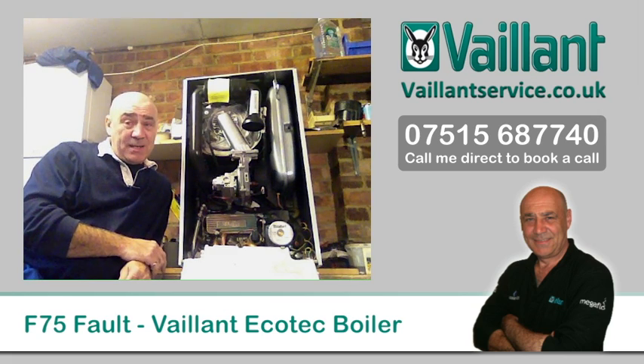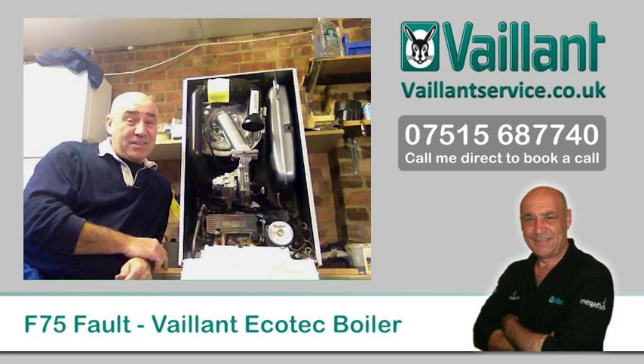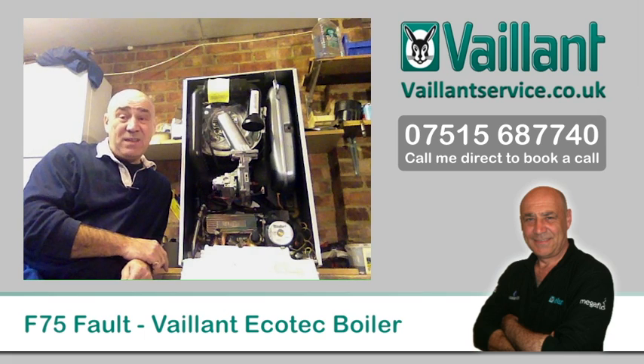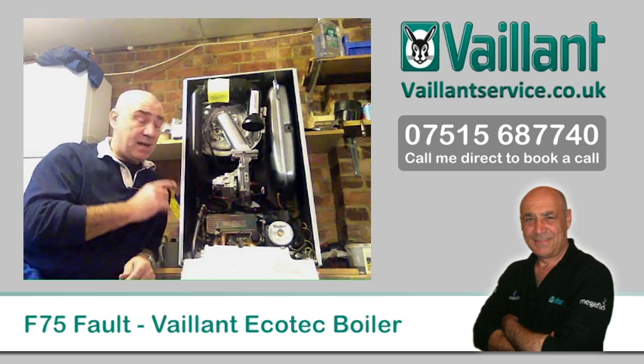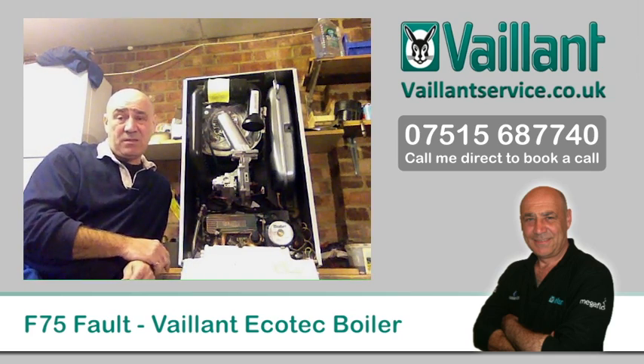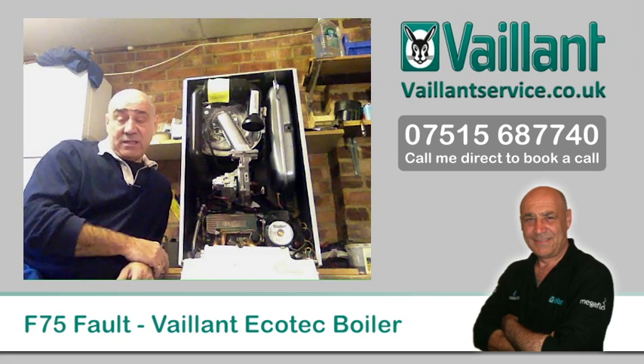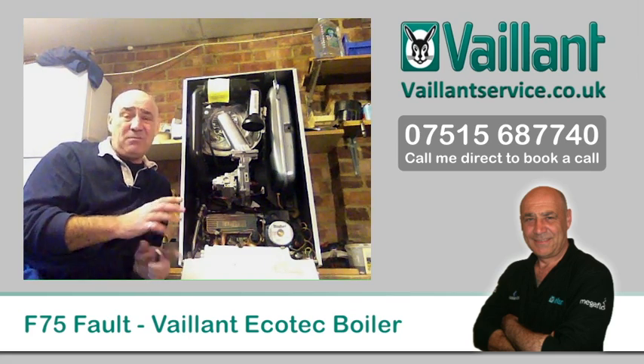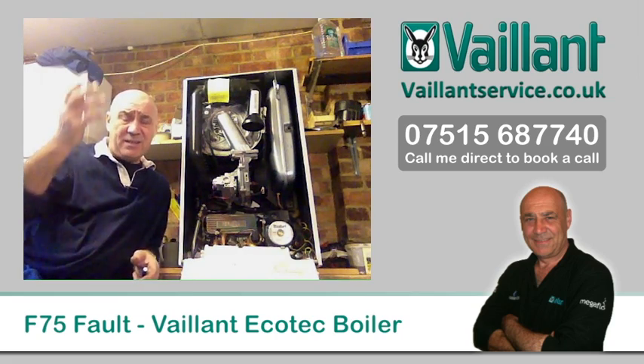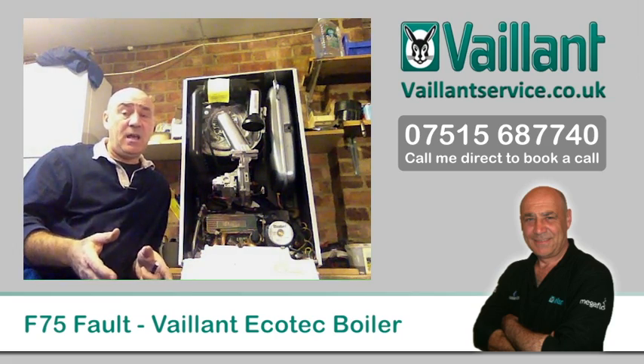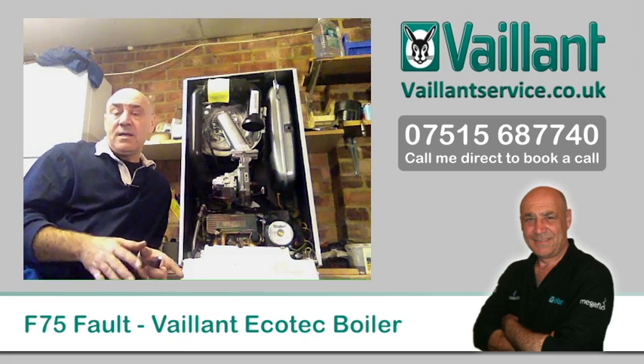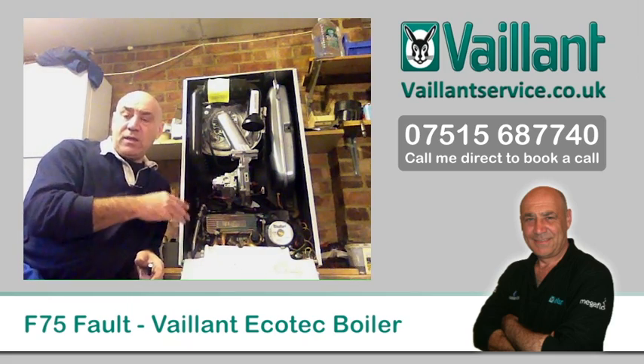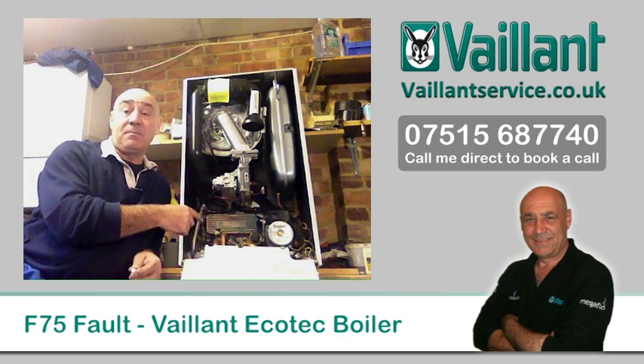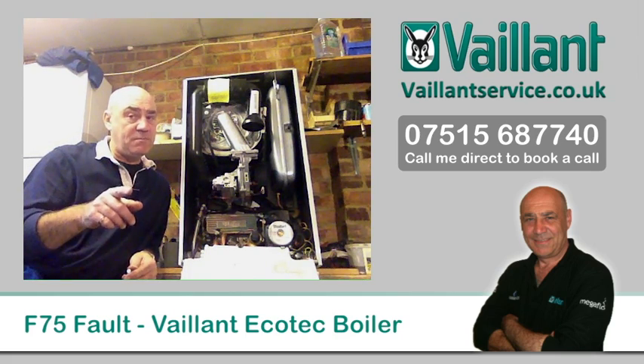Now, generally speaking, you should be able to fix this problem for less than 25 quid. Because I have very, very rarely had to condemn a boiler because the main heat exchanger is blocked. Usually, I can fix this F75 problem without any parts, or with one that costs less than 25 quid. Okay, so don't start jumping in there and ripping the boiler apart and taking this out, changing this and changing that, because it's unlikely to be an expensive part you require. You need to go through the protocol, fix all the things that could be causing that lack of picking up the pressure increase before you start spending money. Very expensive to fix if you don't know what you're doing.